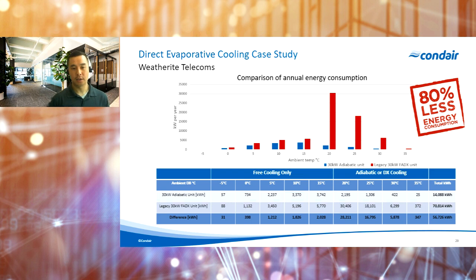So what does that actually show or mean for the overall efficiency compared to the previous DX cooling system that they were using? On the slide, we're comparing the annual energy consumption for both the legacy 30 kilowatt fresh air unit with DX cooling and the new 30 kilowatt adiabatic unit. The top two rows of the table show the ambient air temperatures from -5 to 35, and then the associated mode that we would be operating in based on those ambient conditions.